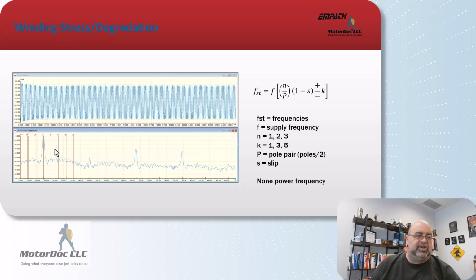And the winding stress signature we derived, originally it's always been presented as being the winding short measurement. Well, the same formula actually turns out to be any type of electrically related issue, like sparking or partial discharge, that causes a variation in the magnetic field. So if I have variable frequency drives and they're not set properly, they'll cause more PD in that gap, and as a direct result, I'll end up with a signature.